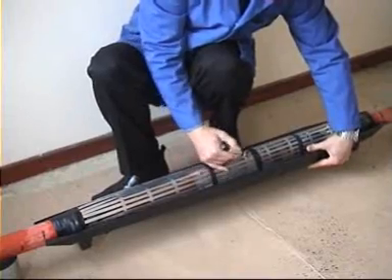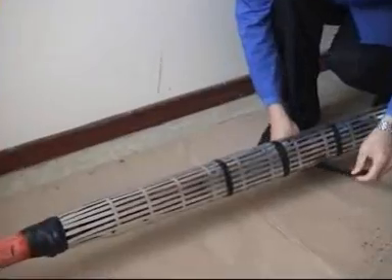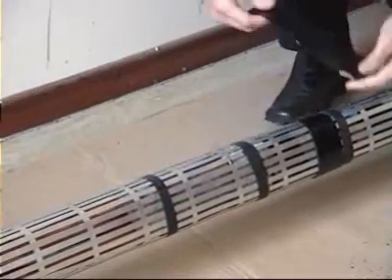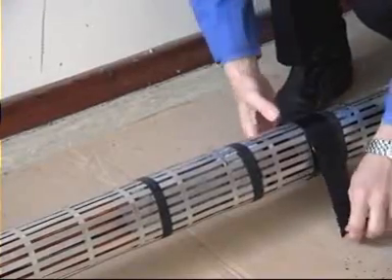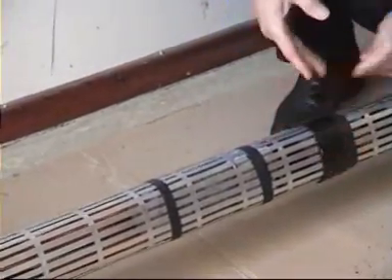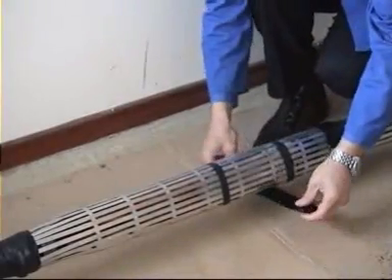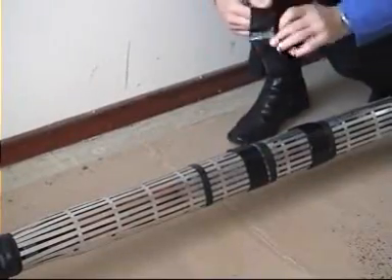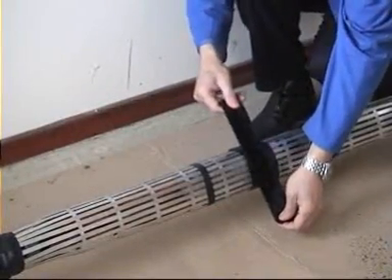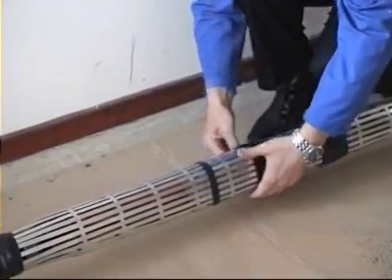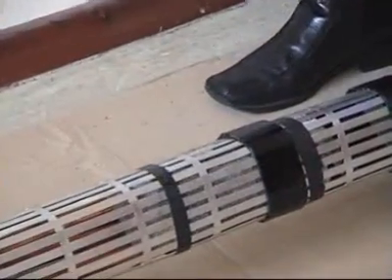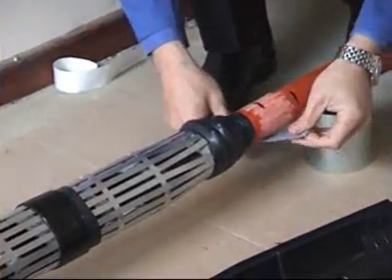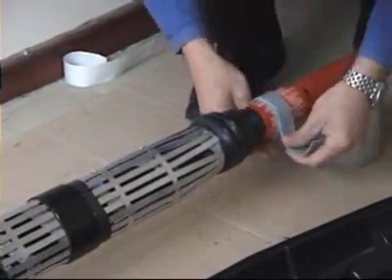Make two further marks on the cable and apply the black mastic tape around these marks. The application of this tape will allow the joint to be spaced apart from the shell so that the resin can fully encapsulate it. Apply a turn of grey mastic tape to the outer sheaths.